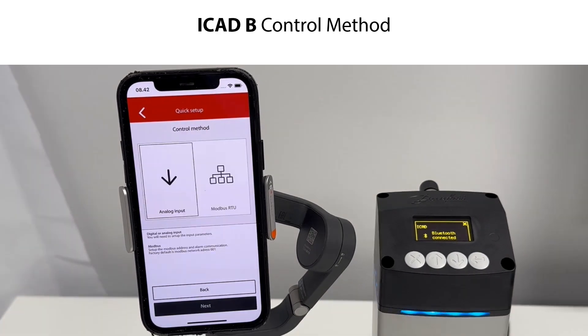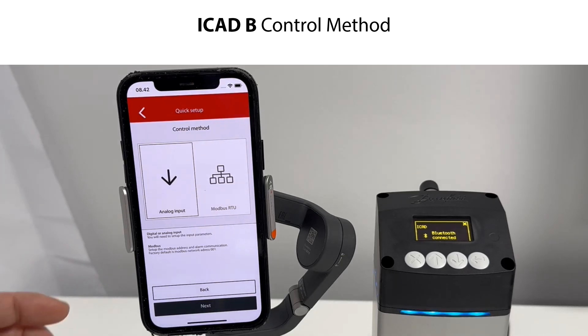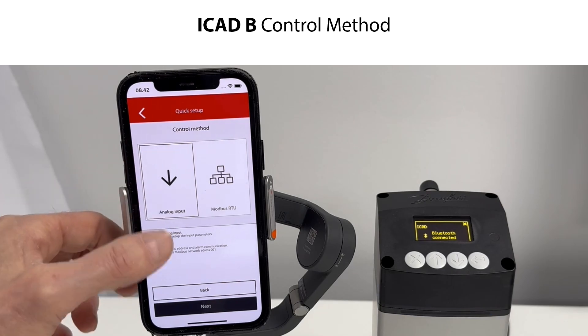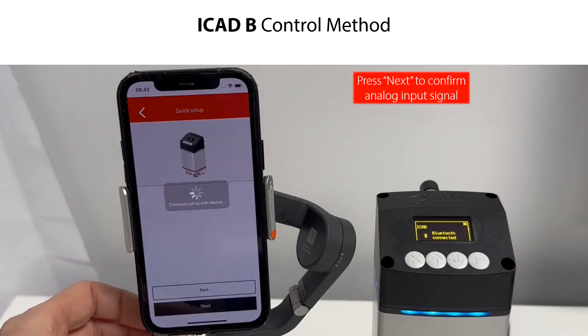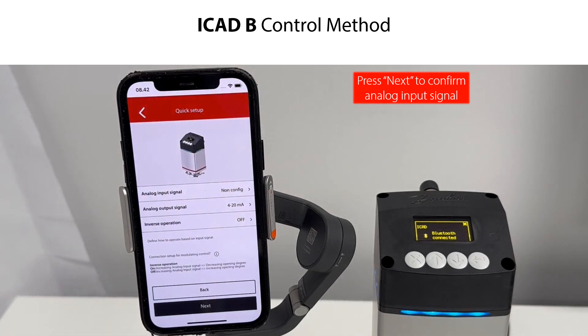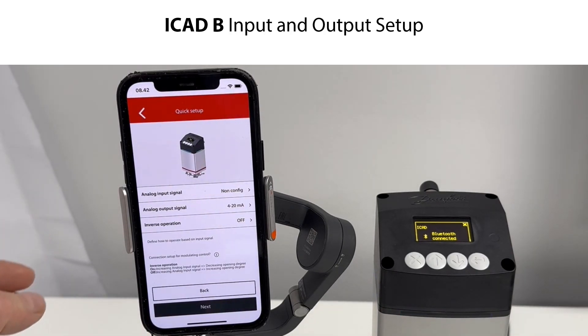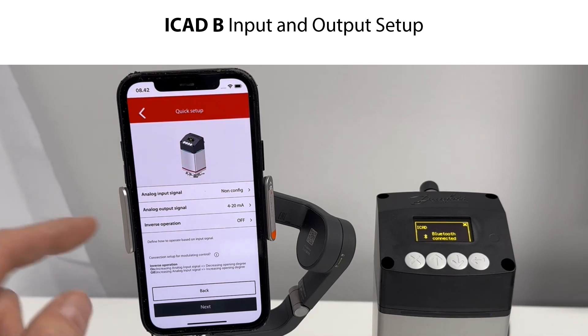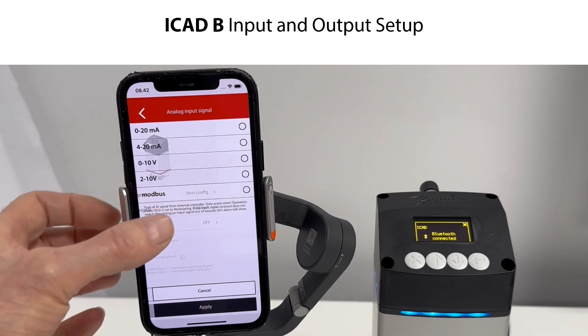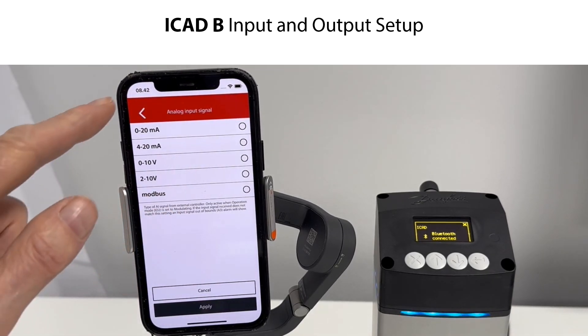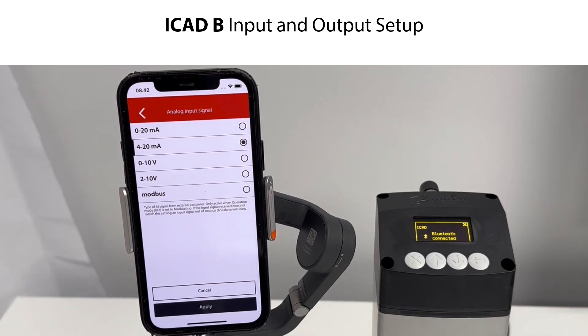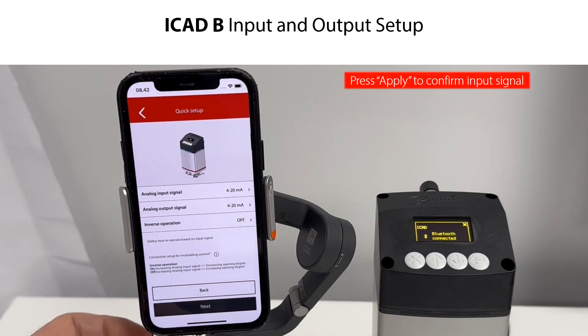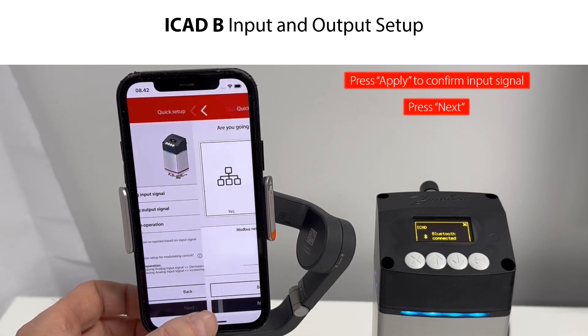The next step is to select the ICAD-B control method. Since modulating operation was selected, you need to define an analog input signal. In this example, we confirm using an analog input signal by pressing Next. You then need to specify the input and output signals. The default input signal is NON CONFIG and the default output signal is 4 to 20 mA. We change the input signal to 4 to 20 mA, confirm by pressing Apply, and press Next to continue.